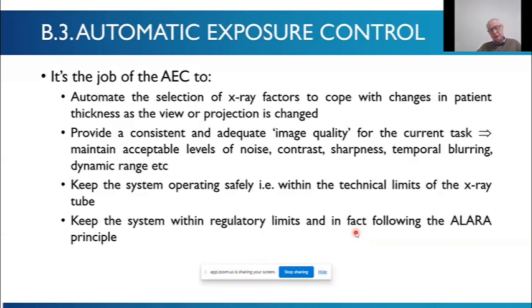Onto the automatic exposure control. A brief reminder of what the job of the AEC is. It's to automate the selection of X-ray factors to cope with changes in patient thickness as you move and make different projections around the patient, to provide a consistent and adequate image quality for your current task, which, as we know, can be programmed for the different tasks. So this means really maintaining acceptable levels of noise, contrast, sharpness, temporal blurring, so that the clinician can get the information that they need to do the task. Keep the system operating safely, i.e. within the technical limits of the X-ray tube, so you don't destroy the tube by going to factors that are dangerous or will harm the tube. And keep the system operating within regulatory limits and, in fact, following the ALARA principle.